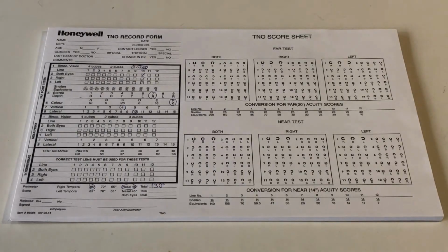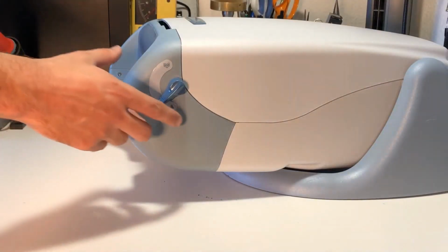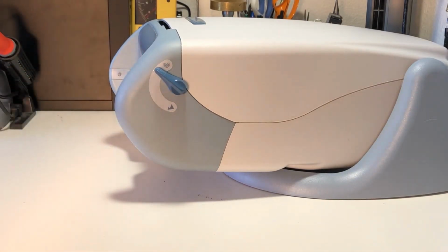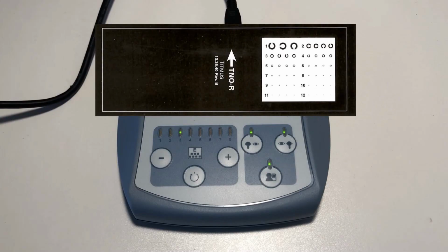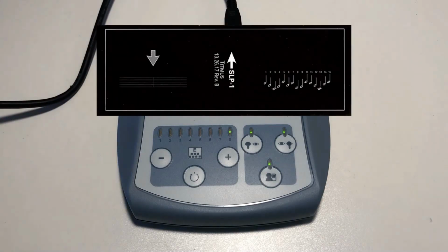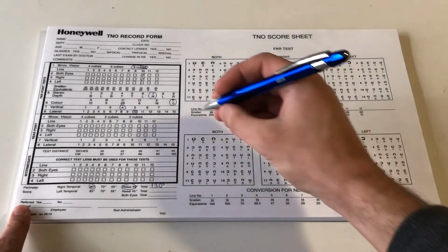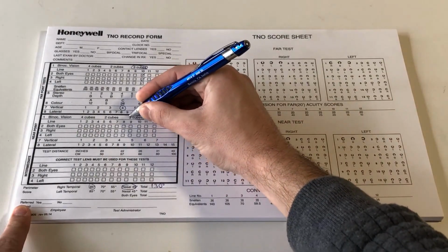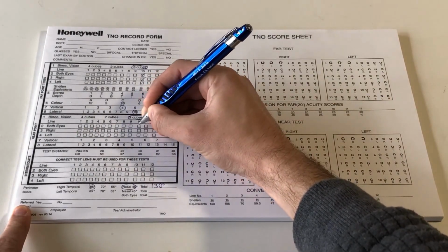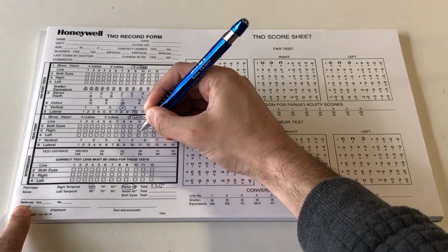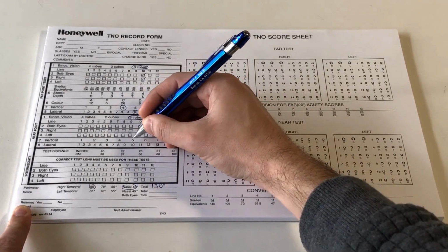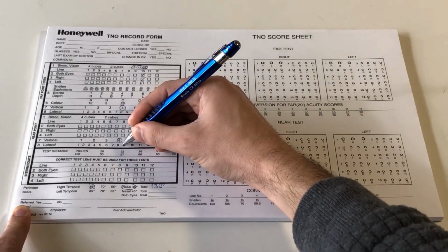Now we will move on to the near point portion of the test. Move the near far lever to the near position and repeat the procedure for slides 1, 2, 3, 4, 7, and 8. Record the results in the near point box of the record form.